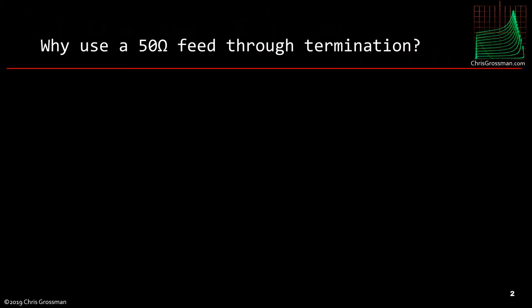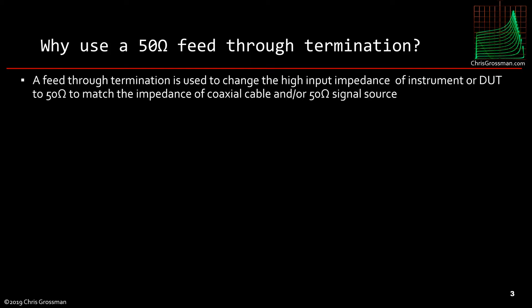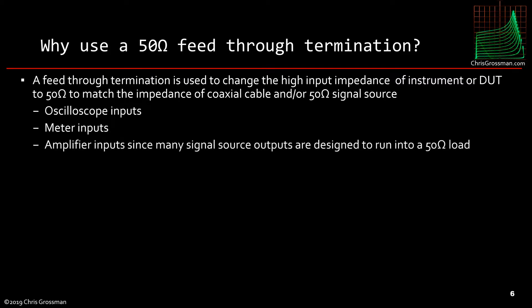Why use a 50 ohm feed-through termination? A feed-through termination is used to change the high input impedance of an instrument or device under test to 50 ohms, to match the impedance of the coaxial cable and/or 50 ohm signal source. An example would be a high impedance oscilloscope input, a meter input, or perhaps an amplifier you're testing with a high input impedance, since many signal source outputs are designed to run into a 50 ohm load.